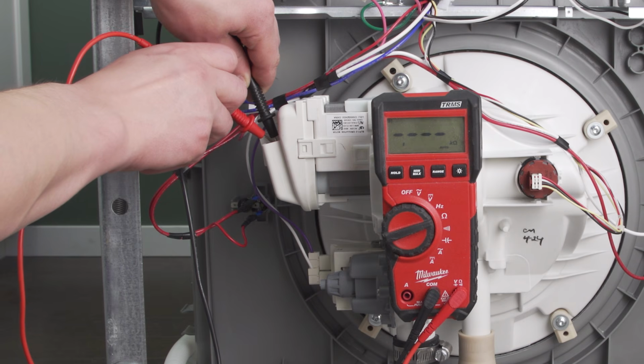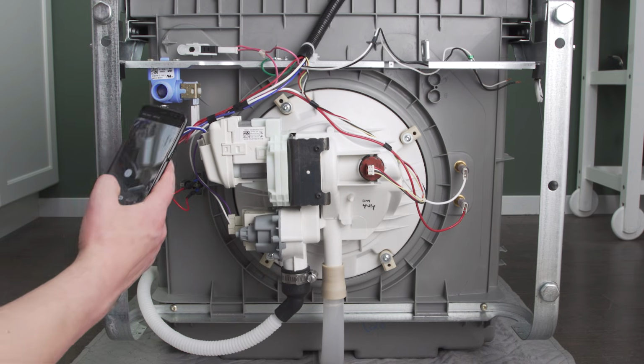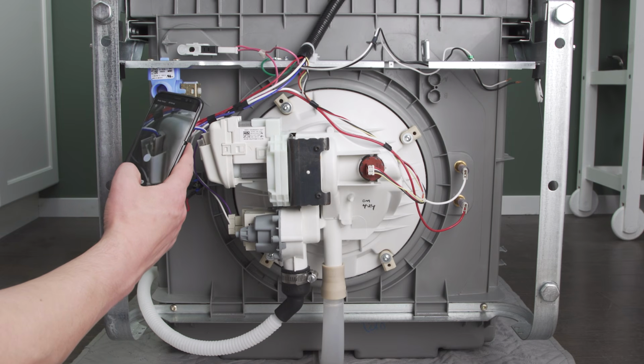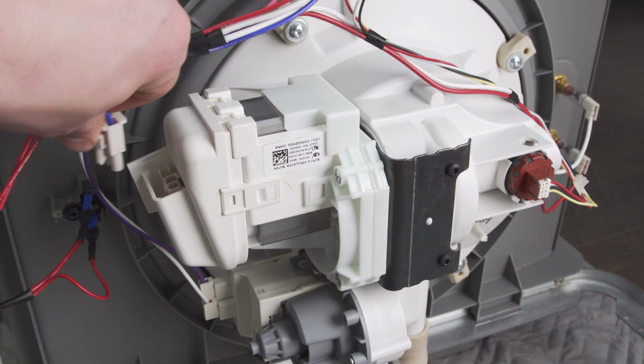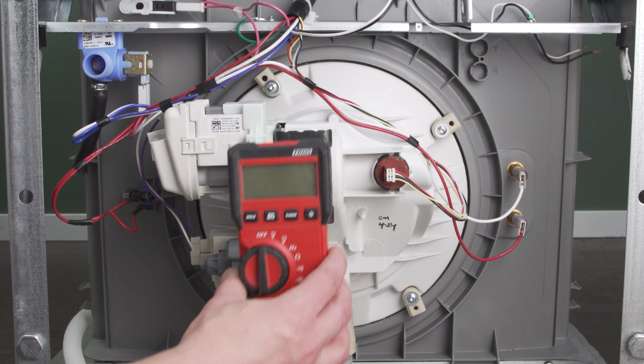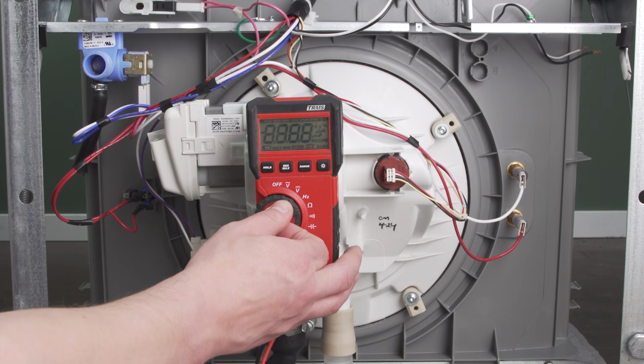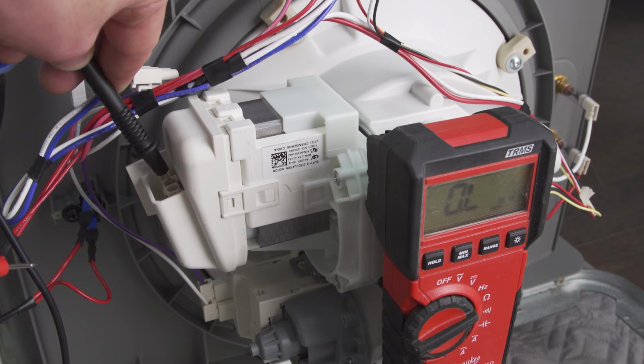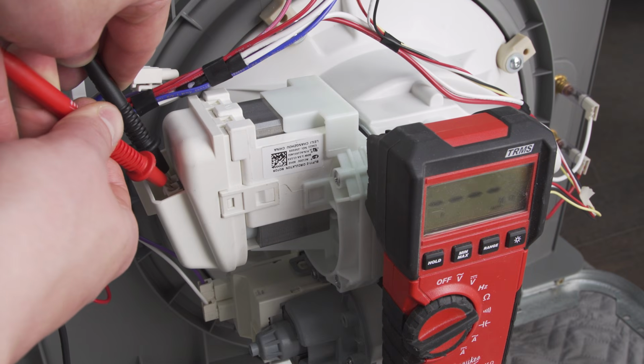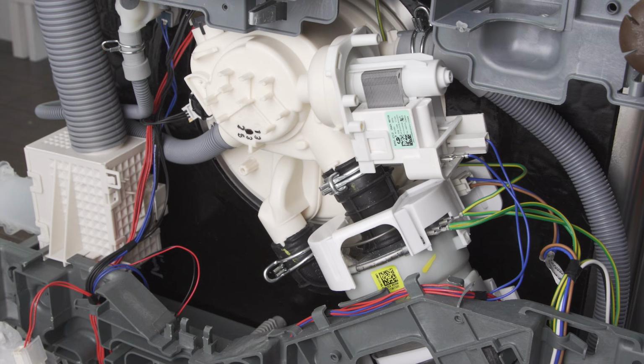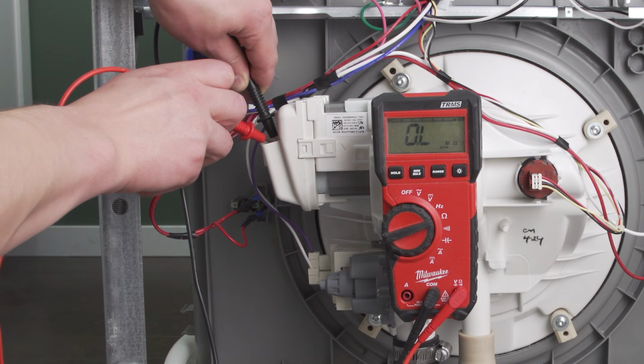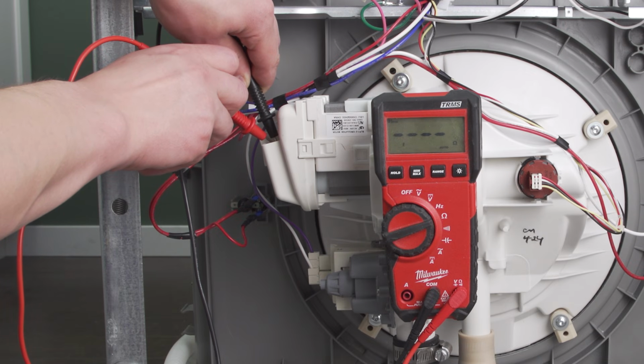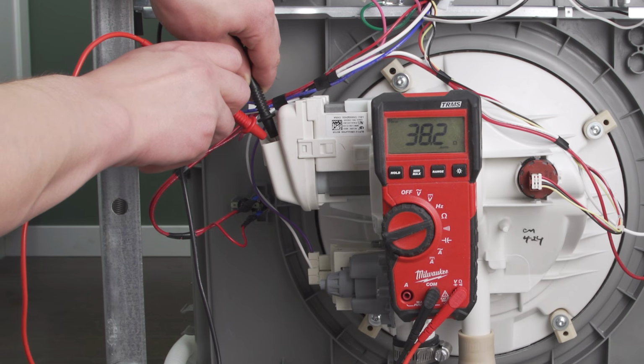We can test the pump motor while it's still mounted in place. It's always best to take a picture of the wires for reference. Now disconnect the wires. Set your multimeter to the resistance setting. Touch each probe to each terminal. If there's more than 2 terminals, then you'll have to test each pair. There should be a resistance reading of 10 to 100 ohms. You might get a different reading between each pair.